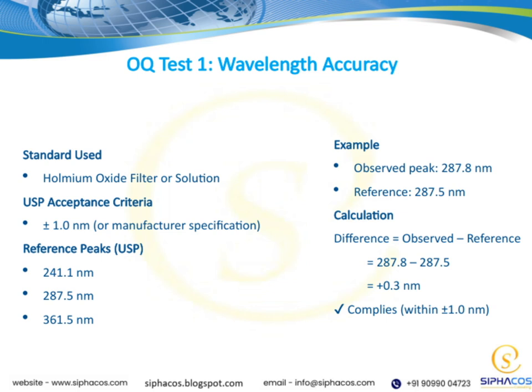According to USP acceptance criteria, the difference should stay within plus or minus 1.0 nanometers, or as specified by the manufacturer. The USP reference peaks include 241.1 nanometers, 287.5 nanometers, and 361.5 nanometers. These peaks help us verify instrument accuracy and ensure our measurements are reliable and consistent.